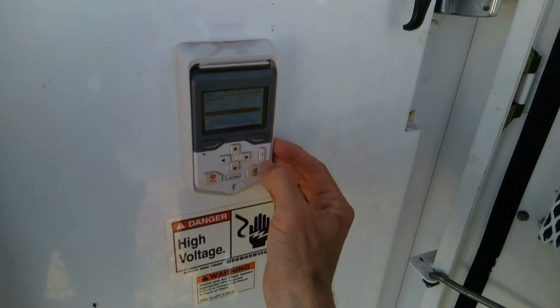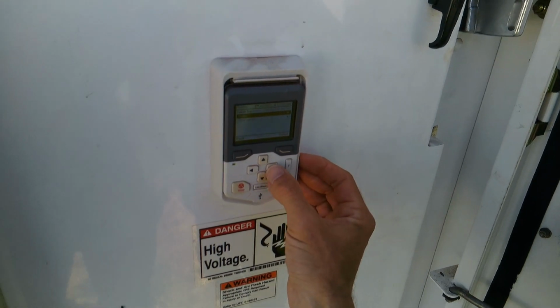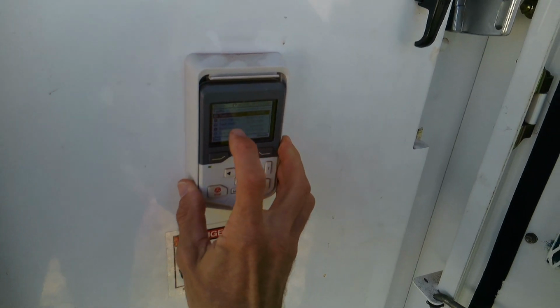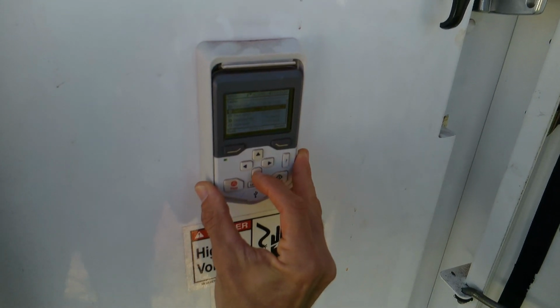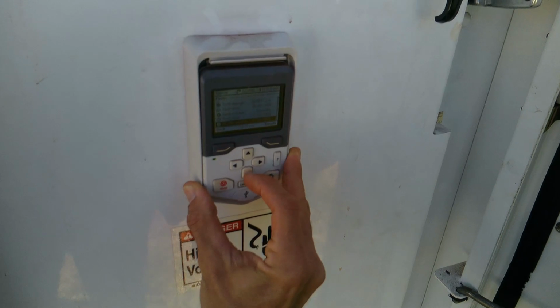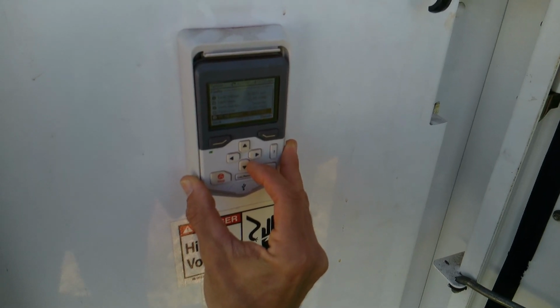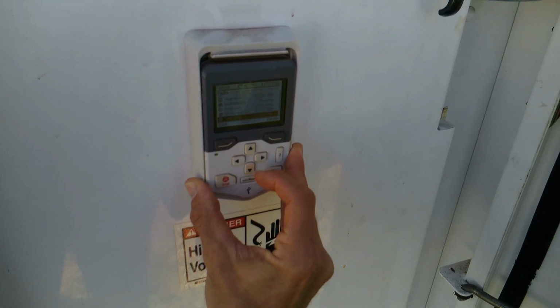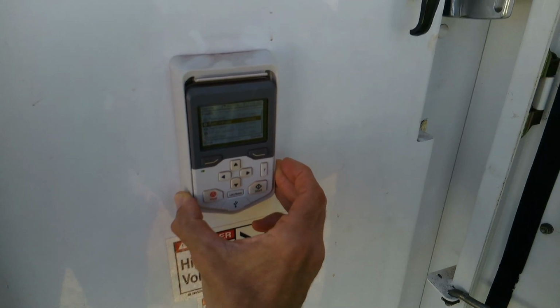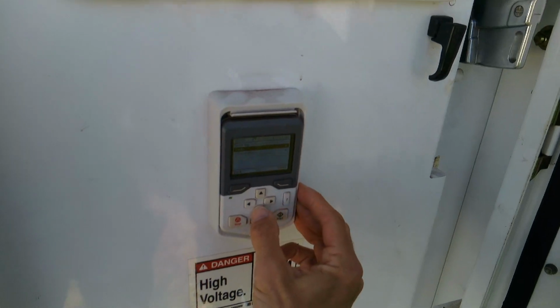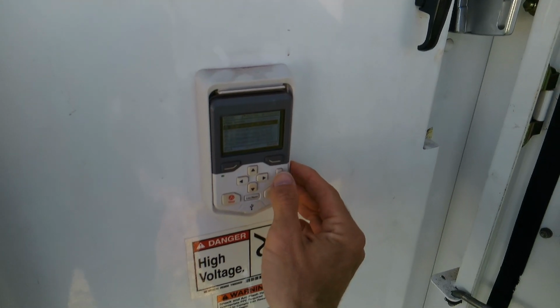It's probably under diagnostics, fault and event log, faults. Earth leak. 1980, earth leakage yesterday. Looks like the internal clock is a little off, but we had an earth leakage yesterday. What does that mean? I'm pretty sure earth leakage is like a ground fault.